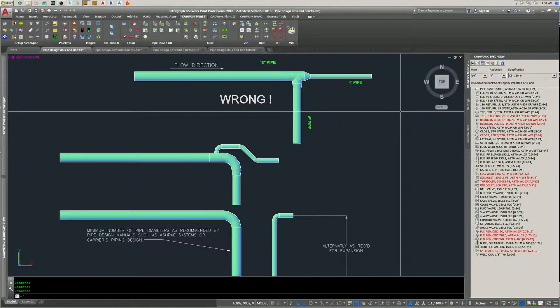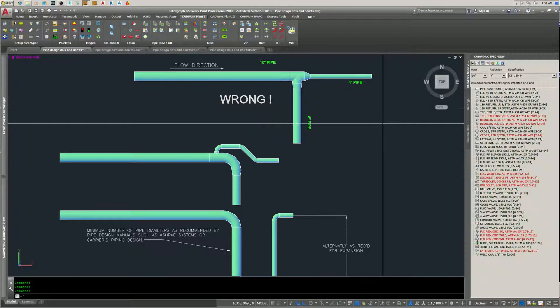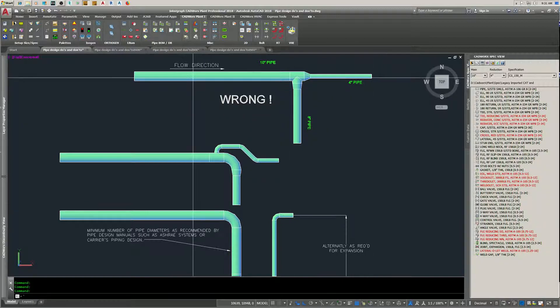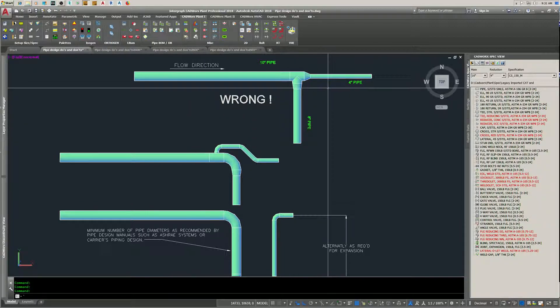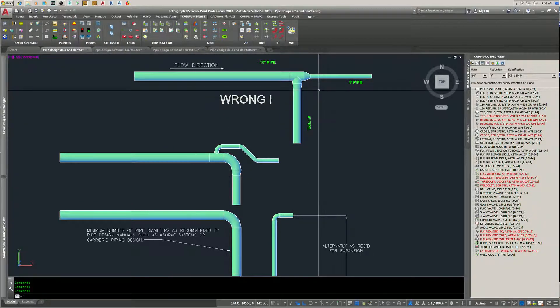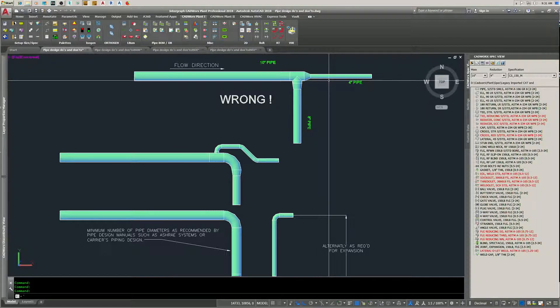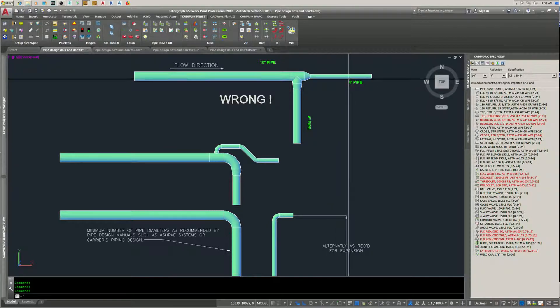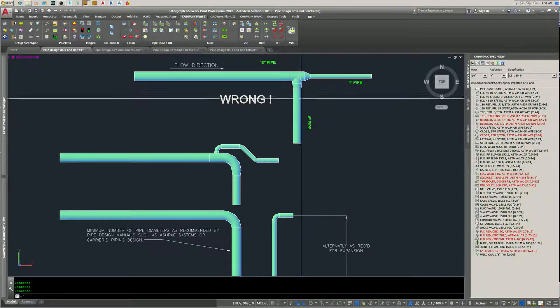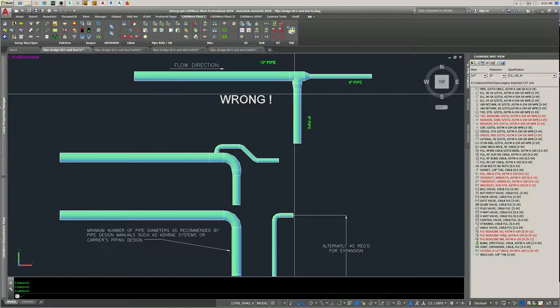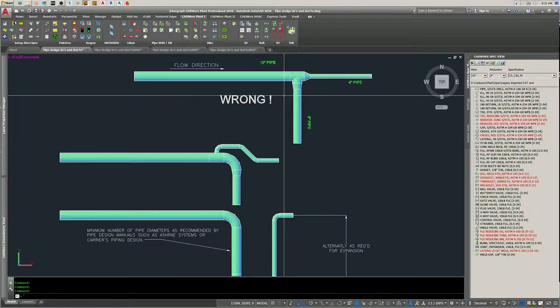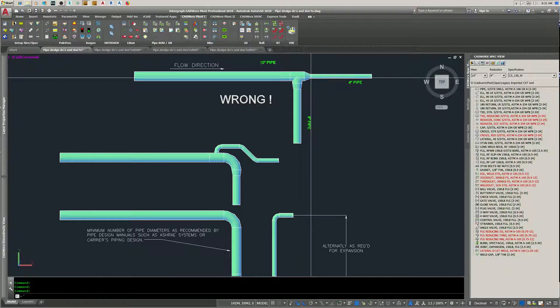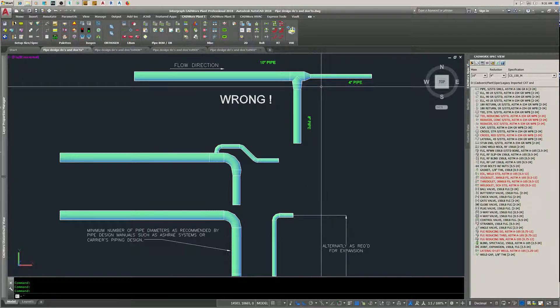A quick look at good piping design practices. I saw this done by an experienced piping designer - he had a two-inch line going out of here with the main continuing on the same size. This is dead wrong, it's a booger to balance.